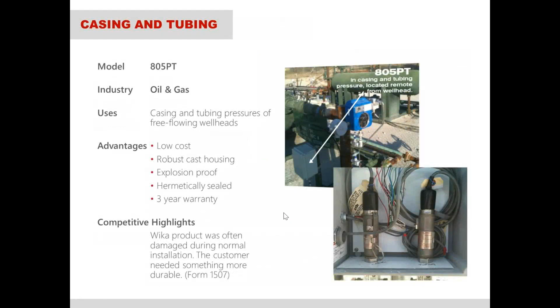Monitoring casing and tubing pressure. This is a very common application for this product as well. This specific application is a customer that, before the 800 series came out, gave us feedback that their operators were using WIKA, and when they put the wrenches onto the housing, they would actually turn it and not put it on the actual wrench flats, and they would destroy the housing in doing so because the WIKA units were fragile and frail and couldn't handle that type of torque. That's why we went to such a durable stainless steel cast housing design, to prevent anything like that from happening where the operators don't install it correctly.